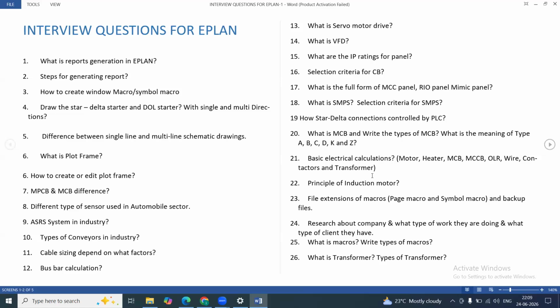We know very well, if I'm talking about analog signals, standard analog signals are available in voltage or current form. Voltage can be minus 10 to plus 10, or 0 volt to 10 volt. If I'm talking about current signals, they can be 0 milliampere to 20 milliampere, or 4 milliampere to 20 milliampere. So sometimes the interviewer can ask, why do we use 4 milliampere to 20 milliampere? Why not every time from 0 milliampere to 20 milliampere?